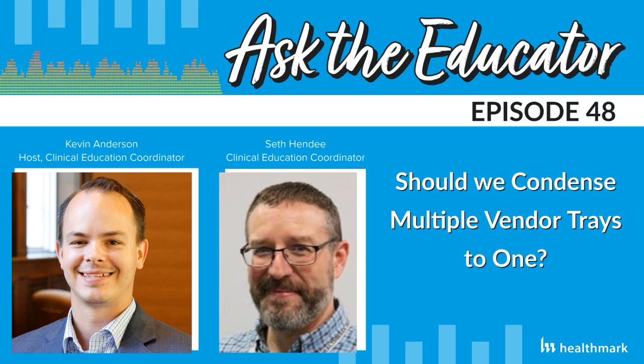That's right. And you know what, Seth? That's very consistent with what I found as well. I even just went to one prominent orthopedic manufacturer that was in my facility, and immediately a couple things stood out to me. One of them says optional instruments should not be added to a pre-configured instrument tray or case unless there was a dedicated universal space or compartment that was included in the design and guideline described below for trays and cases. So without those layouts predetermined, does the vendor even know which ones those are? Does it call it out? Does it specify that these are for optional instruments? So that's number one. It basically is saying, don't do this. Don't put optional instruments in here unless it's specifically designed for it.